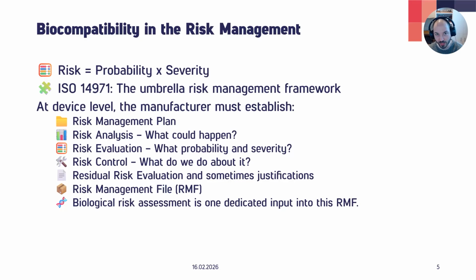And the biological risk assessment follows exactly this logic, and it is one input for the risk management file. Meaning we will analyze the biological risk. Okay, what could happen biologically if we have this device made out of these materials and manufactured in this way? Then we will evaluate, okay, what's the probability that this happens and how bad can it be, basically? So what's the severity? Then what do we do about this? We need the risk controls, and that could include biological testing. And then we will analyze the residual risk, and sometimes we will also provide justifications for that.